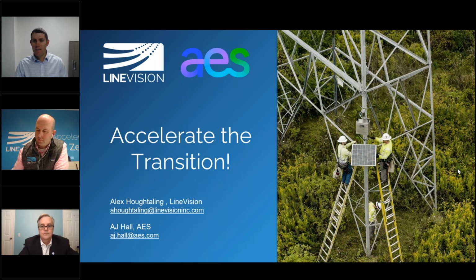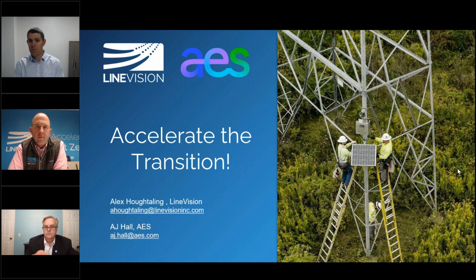And so dynamic line rating builds flexibility into your system. If you have DLR, you can manage someone that has a quick timeline to increase load while building the transmission investment behind that, and do that proactively versus reactively. You have the DLR for the flexibility, and you're able to look at multiple needs versus reacting to them very quickly and shocking your customers with higher rates required to earn the return on that investment. So I think that's how we looked at it.